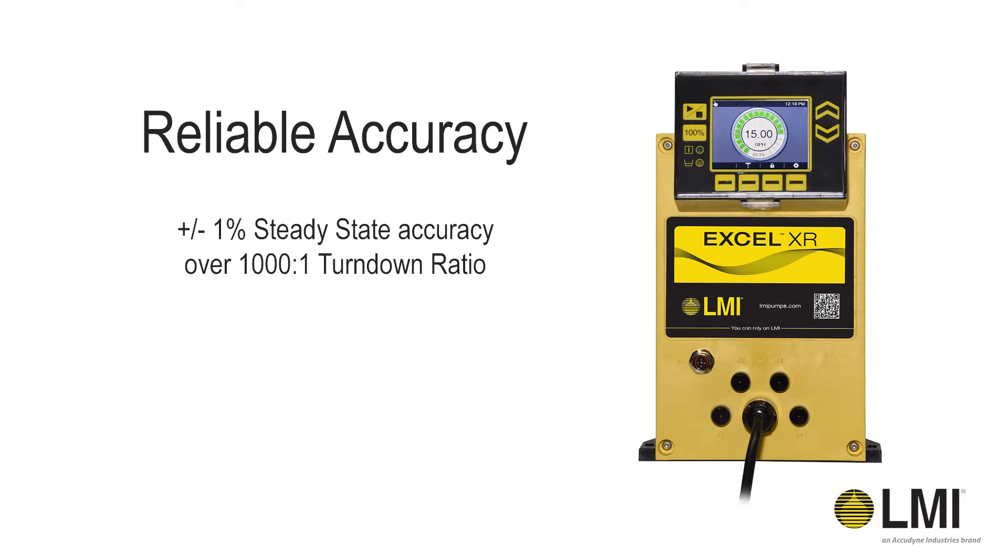In addition to being able to constantly meter chemical into the process, regardless of the set point, you also have unmatched turn down and accuracy. By using this innovative drive design, the Excel XR Pump can achieve a plus or minus 1% steady state accuracy over a 1,000 to 1 turn down ratio.